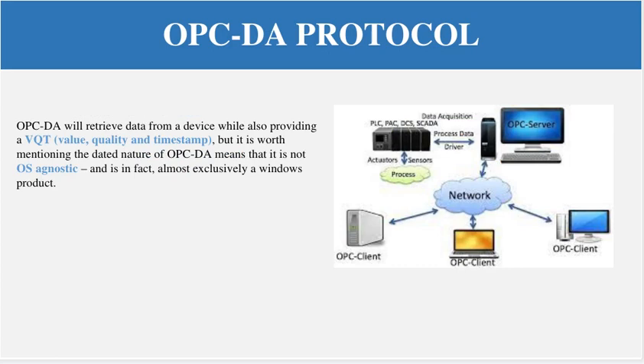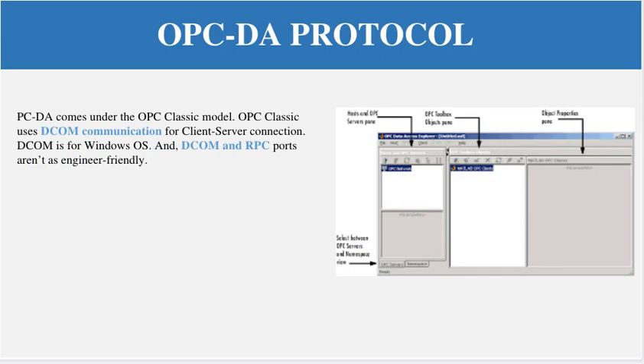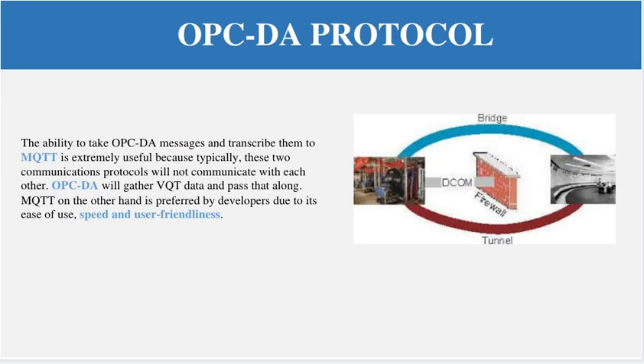OPC DA retrieves data from a device while also providing VQT — Value, Quality, and Timestamp — data. However, it is worth mentioning that OPC DA is not OS-agnostic; it is in fact almost exclusively a Windows product. OPC DA comes under the classic model, and OPC classic uses DCOM communication for client-server connection. DCOM is for Windows OS, and DCOM and RPC ports are not as engineer-friendly. The ability to take OPC DA messages and transcribe them to MQTT is extremely useful because typically these two communication protocols will not communicate with each other. OPC DA gathers VQT data and passes it along, while MQTT is preferred by developers due to its ease of use, speed, and user-friendliness.